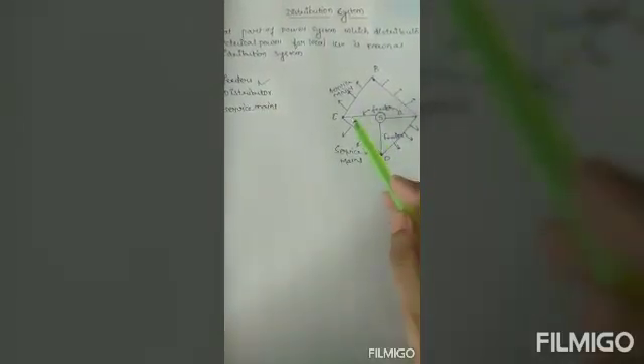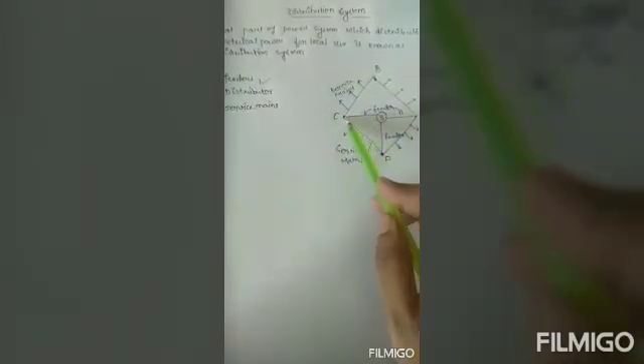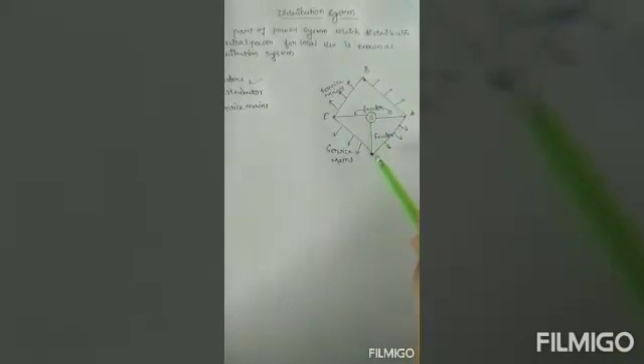In this diagram, we can see the feeders, that is C to A point. Between these two points, this line is a feeder, and S and A, it's also a feeder. Now the next, the substation to the point D is a feeder. The main consideration in designing the feeder is the current carrying capacity.